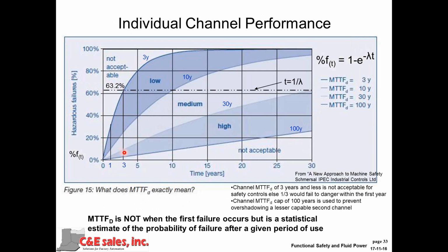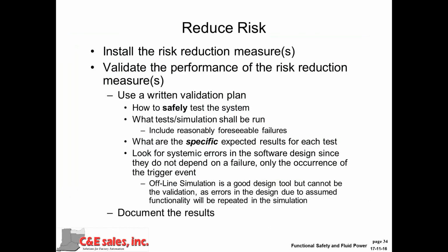You can read it yourself, only maybe a 4 or 5% probability of failure. So you can see how the mean time to failure and the amount of use, basically how many of those cycles to the failure mode that I consume in that time period, determines what the probability of failure during that time period will be.